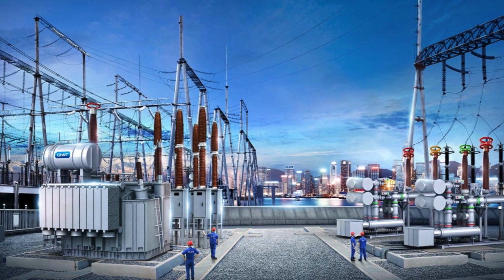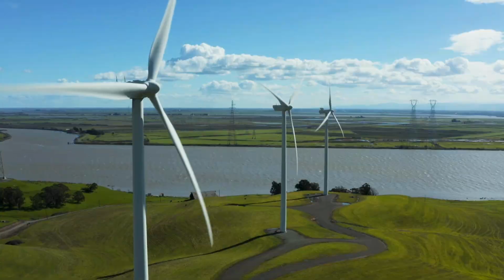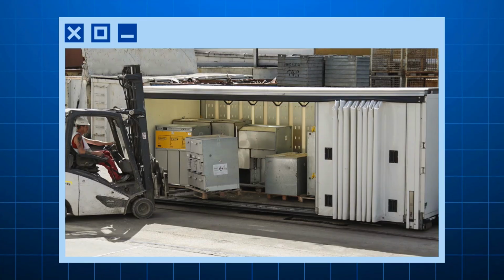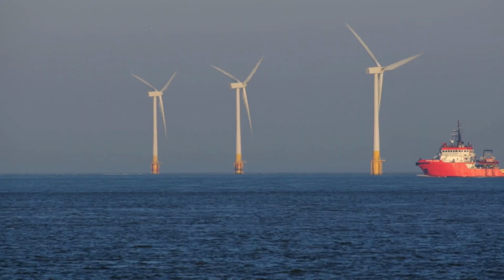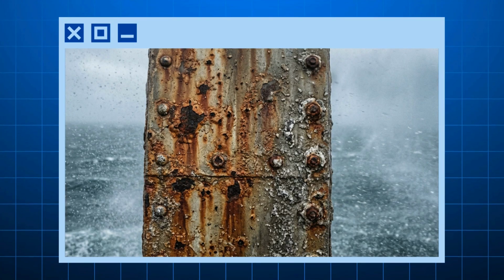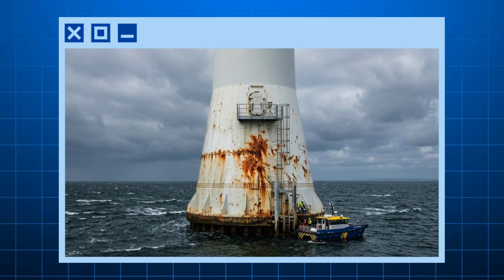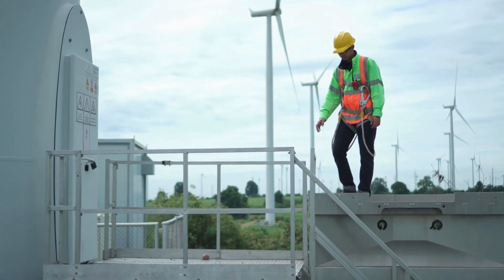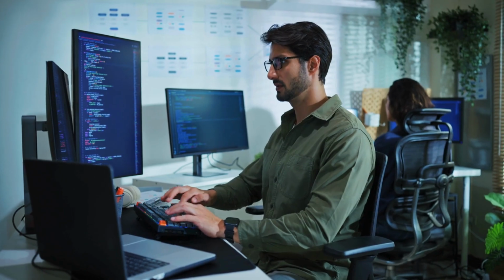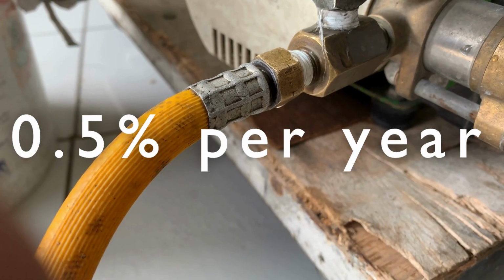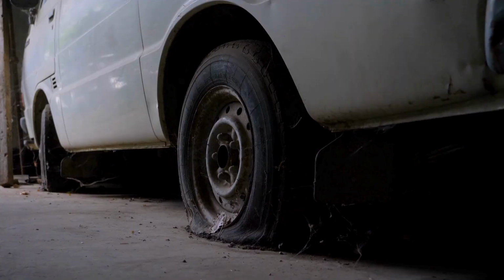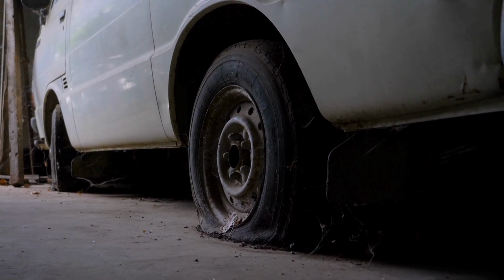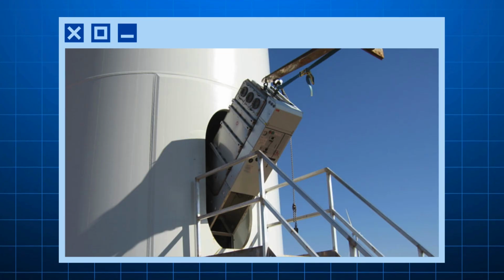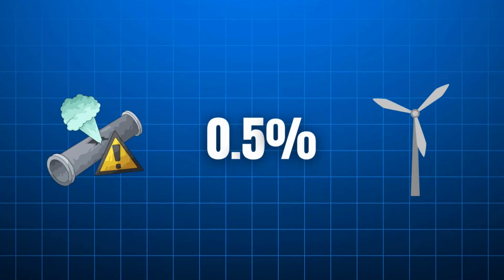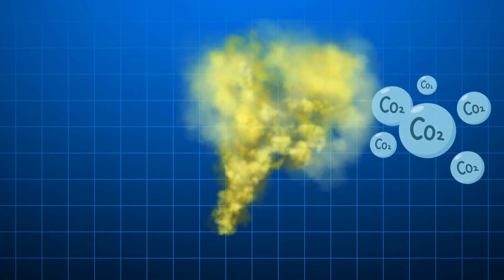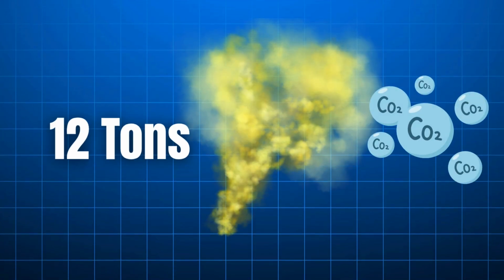While a few sealed units in a centralized coal plant were easy to monitor, the wind transition distributed thousands of individual switchgear cabinets across remote marine environments. Buffeted by high winds and battered by corrosive salt air, these turbines vibrate constantly, causing metal seals to expand, contract, and slowly degrade. Industry estimates place the resulting leakage rate at about 0.5% per year. That sounds negligible, like a car tire slowly losing air over 6 months, but a single turbine switchgear cabinet can hold 100 kilograms of gas. A 0.5% leak from just one machine releases the equivalent of 12 tons of carbon dioxide every single year.